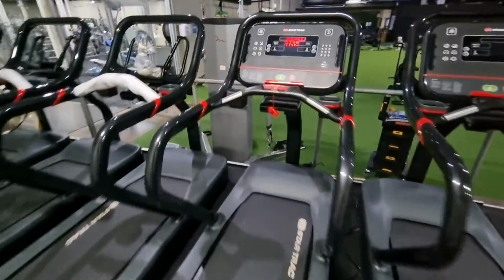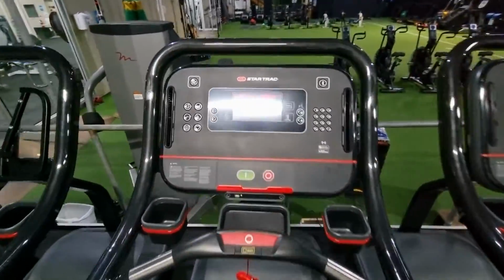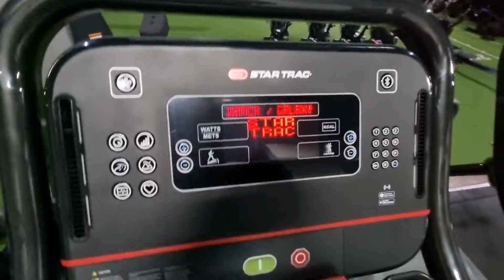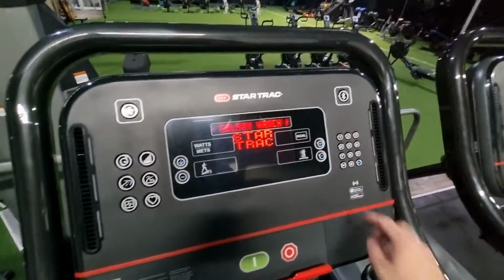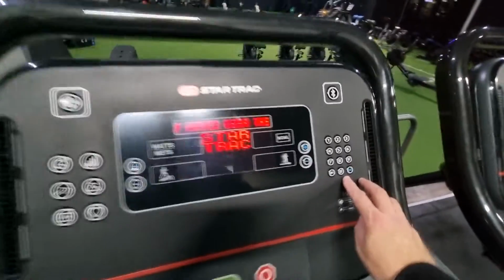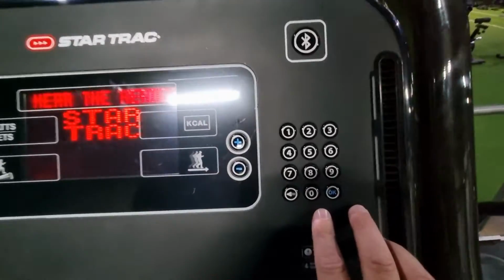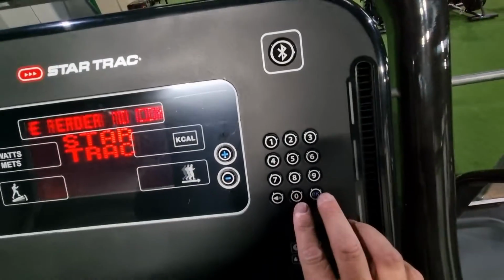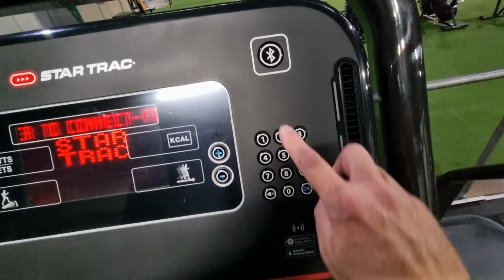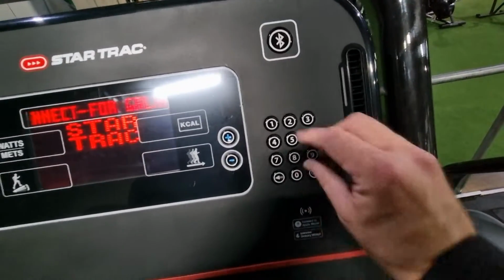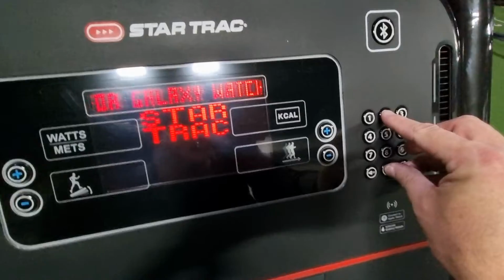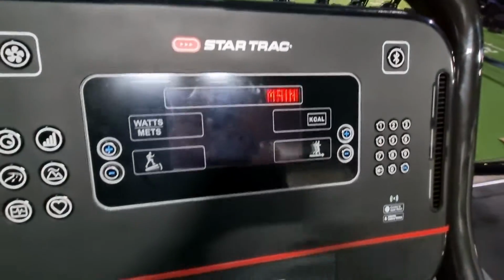So with these, when you install them, if you just power them up, turn them on, you come up with this start screen here. What you have to do is press on this keypad here to get into maintenance mode. You have to press 0, OK and 2. So 0, 2 and OK all at once. If I just hold these three, press them all at once, then it goes into maintenance mode.